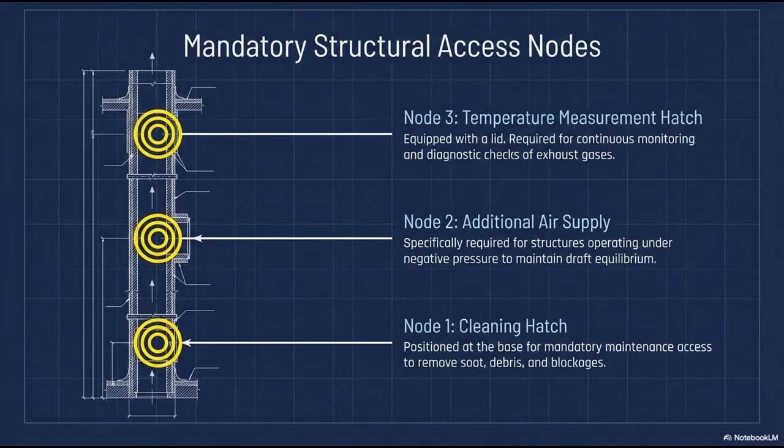So what does this all mean? How do modern engineers actually solve this respiratory crisis for the building? We can't use the old brick, going up the roof is too hard, and we can't go out the side. They solve it through a masterpiece of fluid dynamics and thermal engineering known as the LAS, which, going back to your point about international standards bleeding together, stands for Luft-Abgas-System.